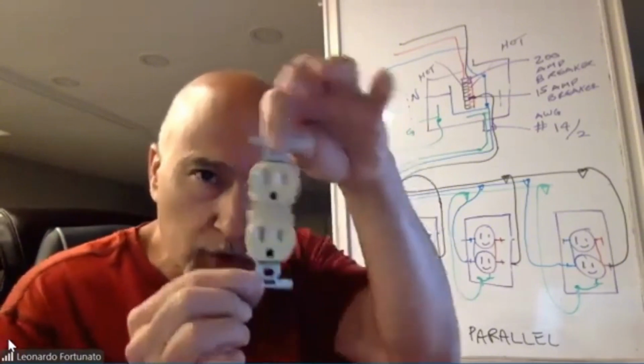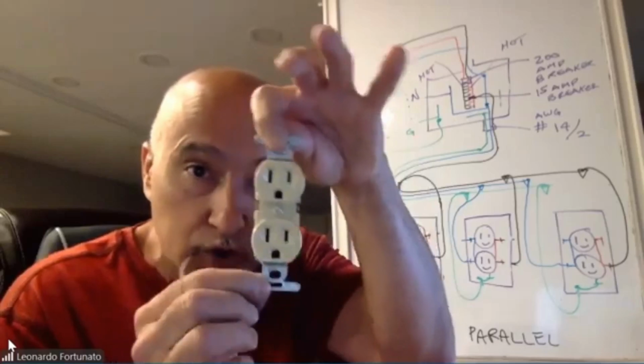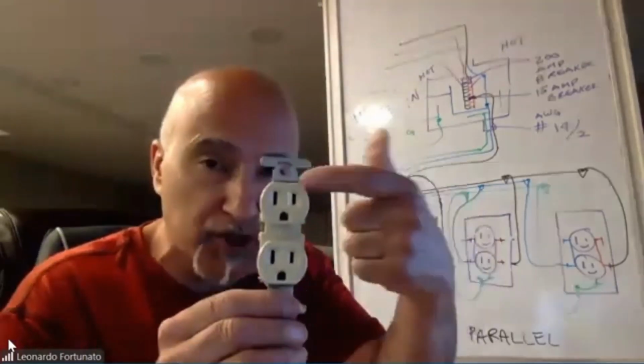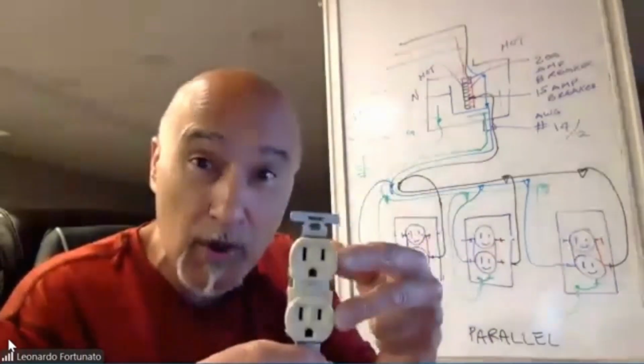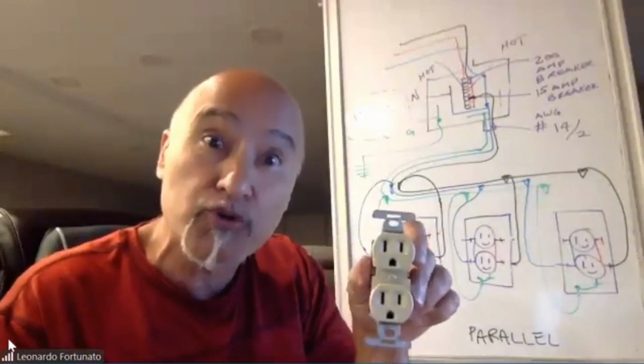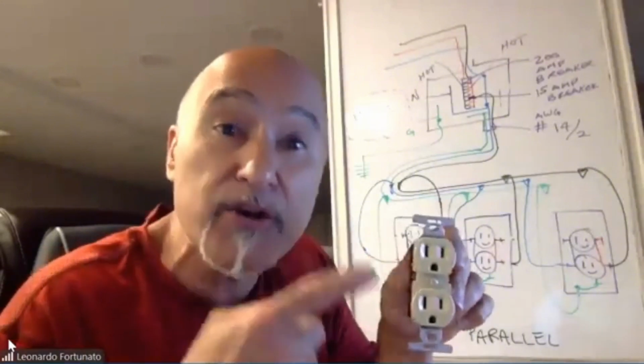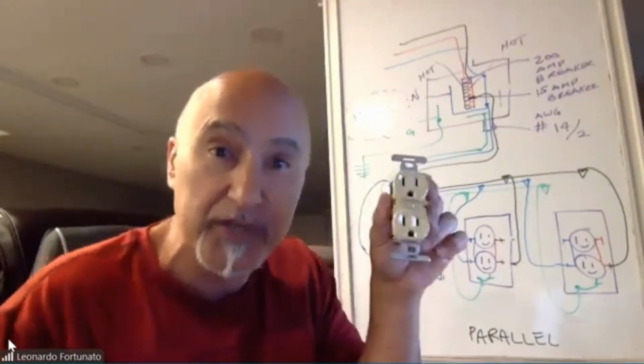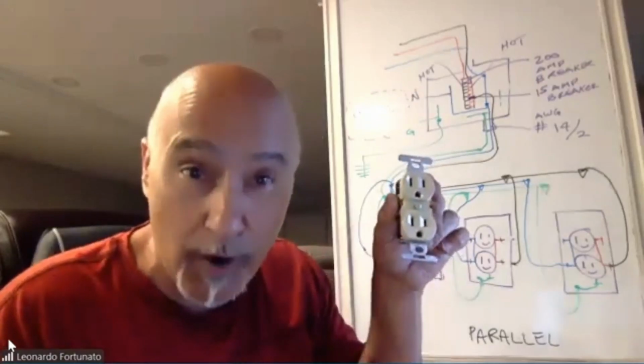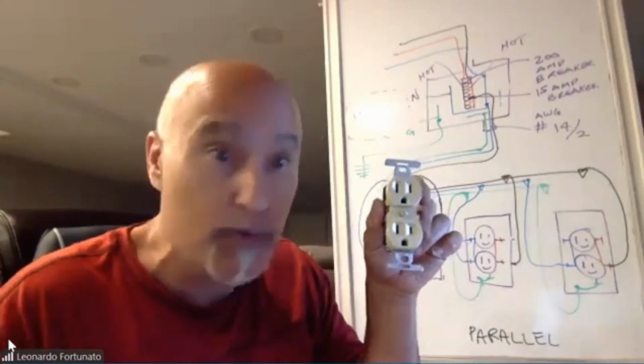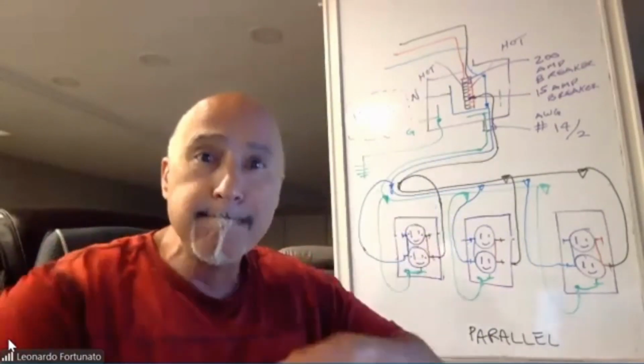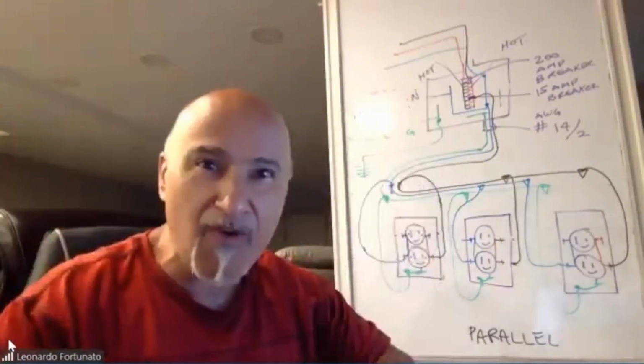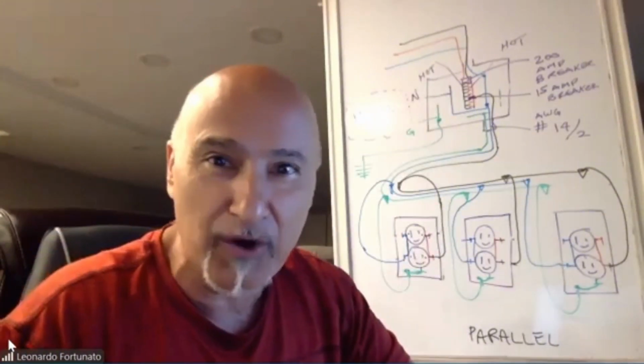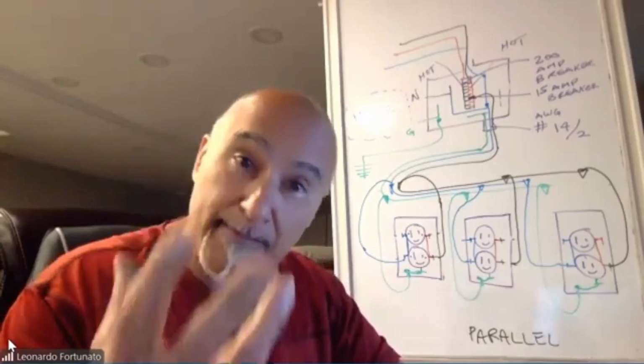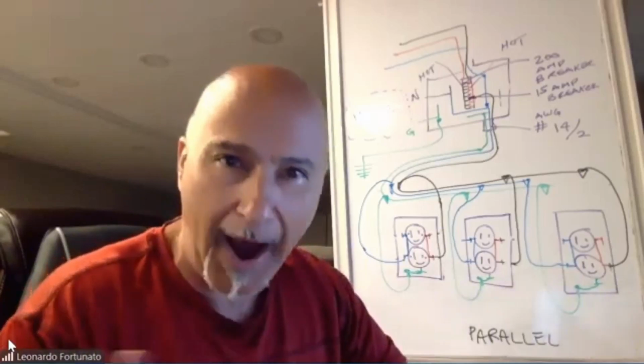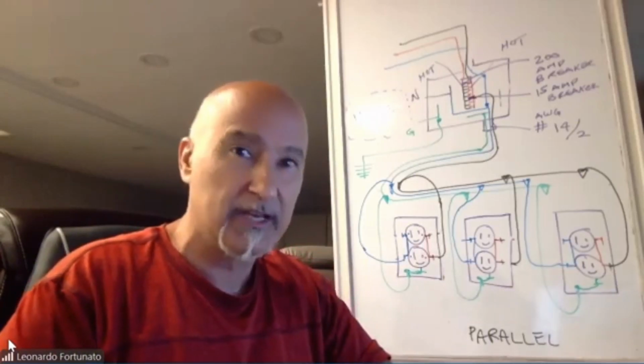If we don't do anything at all to the receptacle and we bring power to the top and to the bottom, what we just did is instead of bringing 120 volts to this receptacle, we brought 240. Whatever you plug into this is going to go boom, and you're going to get smoke coming out of your equipment because it only requires 120 volts.